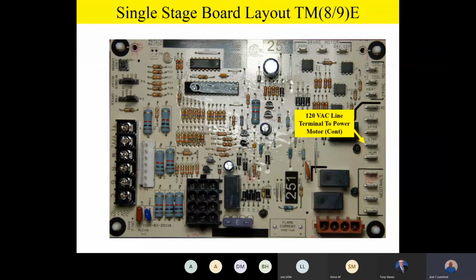And now the reason I'm stressing this is the fact that from a safety standpoint, don't presume that that motor's not energized just because it's not running on these types of furnaces. And so from a safety standpoint, we always recommend you shut the power off and let it sit at least 10 minutes before you take that module off in the back of the motor, because they've got some really big capacitors inside that motor control on the back of that high efficiency motor that'll hold high voltage for several minutes.